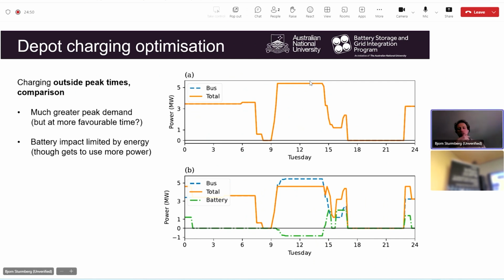The other thing I should point out, just while we're on the fact that the load has been pushed into the middle of the day here, is that we've not modelled any solar being installed on the bus depot. And we've done that because we are looking at the feasibility, or the most challenging conditions, for a bus fleet, which needs to operate throughout the year under any weather conditions. So there's a great opportunity here to install solar on the depot, which indeed was done in Leichhardt, which will contribute both financially, but also in terms of the loading on the distribution network during this middle of the day period.